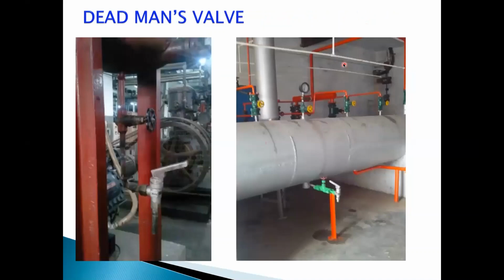The second part is leakage. As I talked about ammonia toxicity, whenever we are draining something from the plant, leakage of ammonia is possible. Most critical is draining the oil. When you are draining the oil, you are opening the valve, so it is possible that ammonia also comes along with the oil. So what has been done is to provide a spring-loaded valve, also called a dead man's valve. A dead man's valve is a valve that, in case of any accident where the person operating it becomes unconscious, closes automatically. It is a spring-loaded valve.